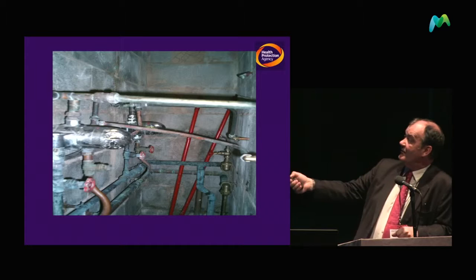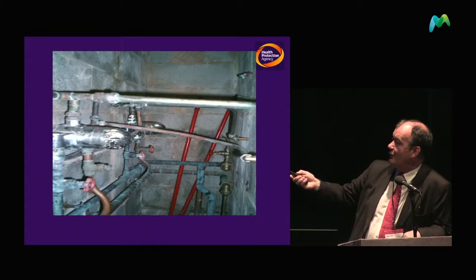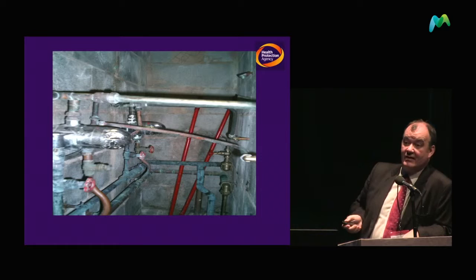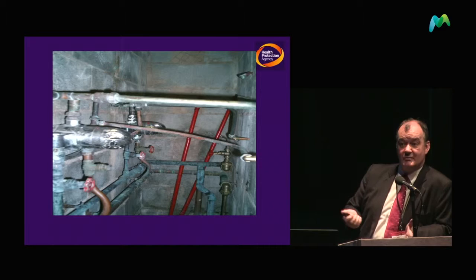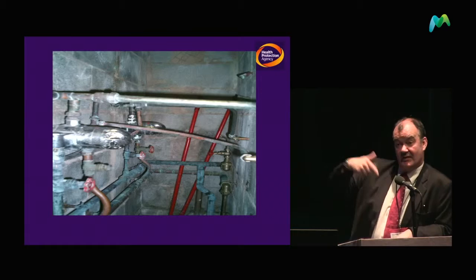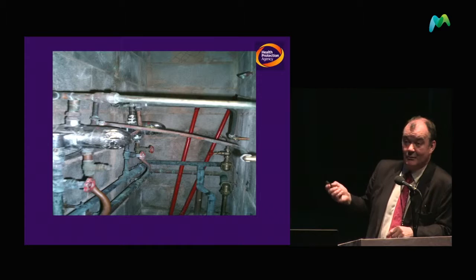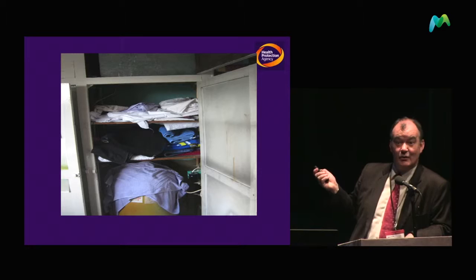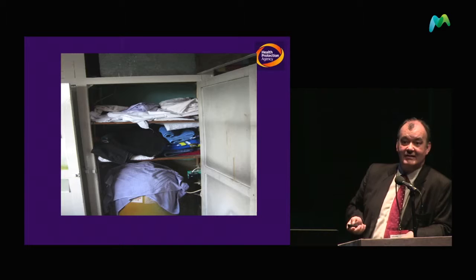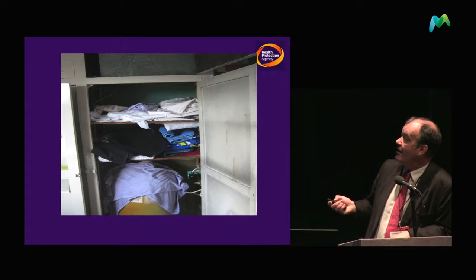Another example: a TMV valve nicely insulated but nothing else insulated — cold water pipes and hot water pipes all mixing in the same area. The ambient temperature in that place was 35 degrees with no insulation, so the cold water was being heated to an ideal temperature for Legionella to grow. Although the TMV was working properly, the water going into it was already 35 degrees and the amount of mixing was minimal.